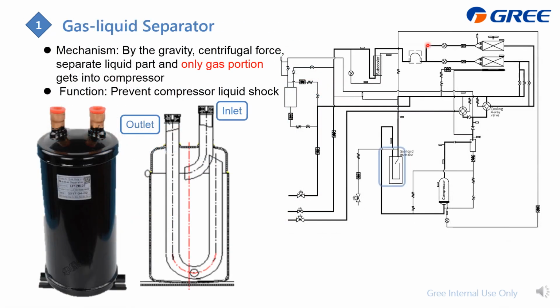Gas liquid separator located here. Here is the appearance. You have two pipes. From this sectional view, you can find that here is the inlet and here is the outlet. The function of this one is that gravity or centrifugal force will separate the liquid part, which will accumulate here, and only the gas will flow up and through this tube, and from here get outside, into the compressor.